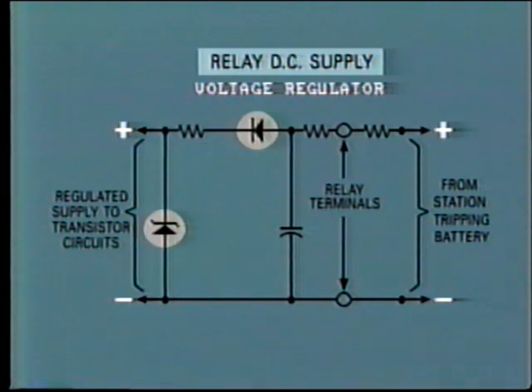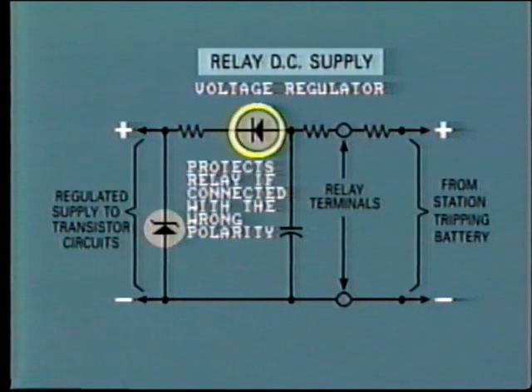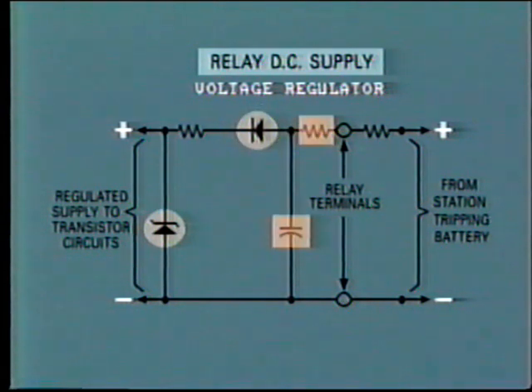This circuit also includes a limiting diode which protects the relay by blocking all current flow if the terminals are connected with the wrong polarity. And a filter is provided to absorb any transients that are contained in the incoming DC supply.